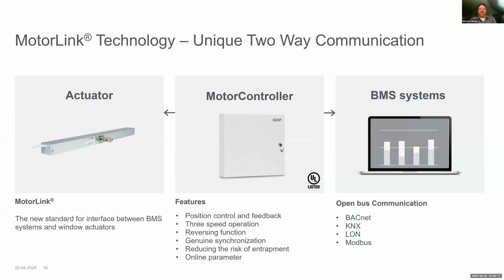So one of the technologies that can help with sustaining the system and communicating throughout the entire project to make these concepts happen for thermal comfort and manual and automated control is the MotorLink technology. It's a unique two-way communication between the actuator, motor controller, and the BMS system. So with this, the motor controller is kind of the center for all of this. And that's where all of the features come in with position control and feedback.